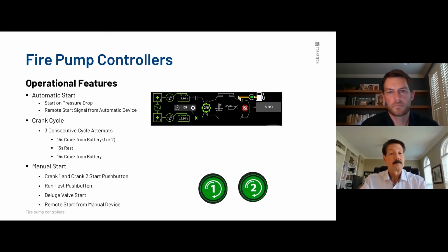All right, here we are. Crank 1, crank 2. Again, operational features. We start on a pressure drop. We can do a remote start signal from an automatic device. Typically, what will happen is if you do have an automatic start, it will literally sit there and crank 3 consecutive attempts on each side. So it'll crank for 15 seconds on number 1.